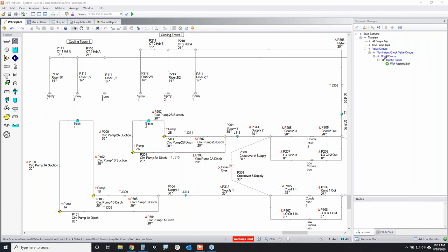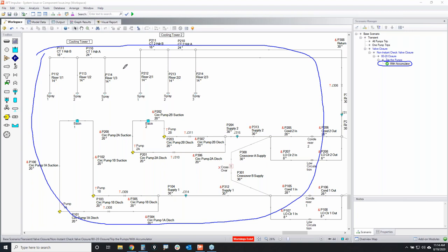And then last but not least, if you need to, try some other surge mitigation methods where you try using other surge equipment like relief valves, vacuum breaker valves, gas accumulators, surge tanks. Each of those has a different function depending on the scenario that you're trying to model, and you just keep stepping your way through bit by bit. You don't need to apply all the changes all at once. Make one change, look at your graphs, do your animations, see what's going on with your results, and then try the next thing, and the next thing, and the next thing. And so water hammer analysis, that's all part of it. It's a slow step change through the process to analyze what's going on in the entire system so you can prevent failure.